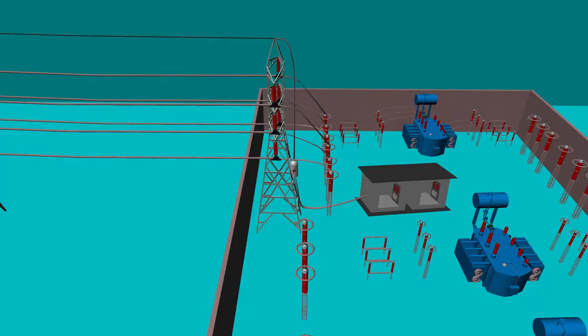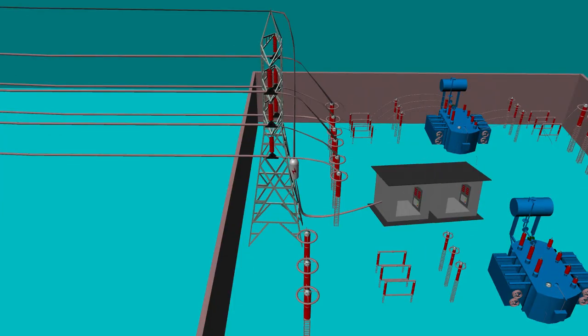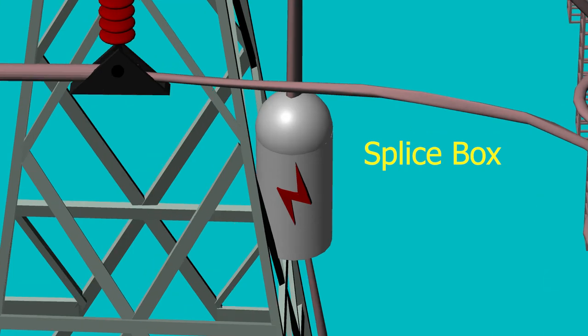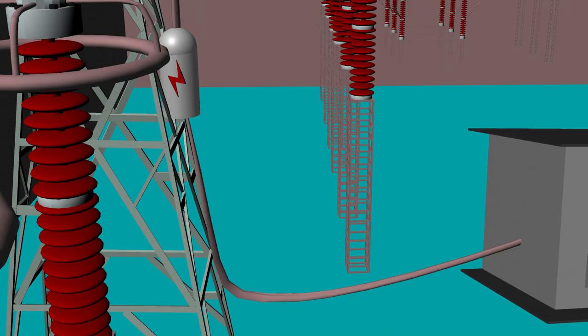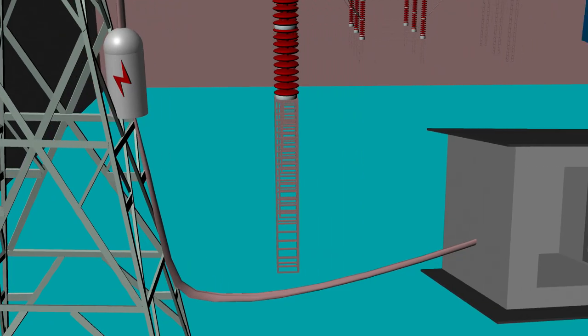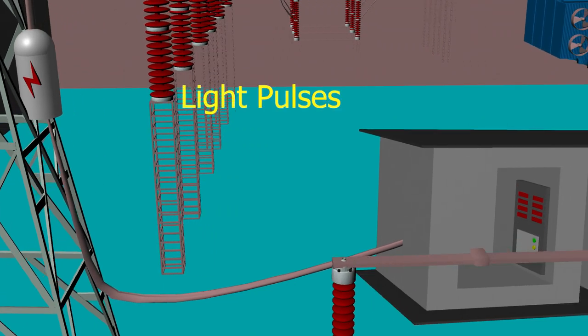These strands basically perform the same function as the earth wire. OPGW is connected to the control room in substation through the splice box installed on the tower. Inside the substation, inside the control unit or receiver side, the data transmitted by optical fibers in the form of light pulses is converted back to electrical signals for further use for protection and control purposes.